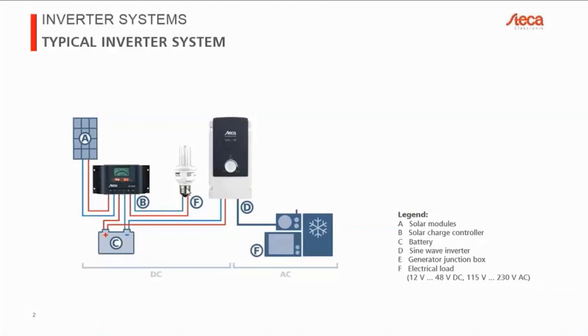This is typically a good idea if you have a house, for example, or a cottage where you can maybe put your lighting and your refrigeration on a DC line on a separate circuit, because like this, you can have all the loads which are running many hours per day. So, for example, lighting or refrigeration, cooling, you could have those running on a DC circuit. And then you can use your other loads, which you might only be using periodically. So, for example, in your kitchen, maybe your television, etc. You could use those on an inverter on a separate AC circuit.